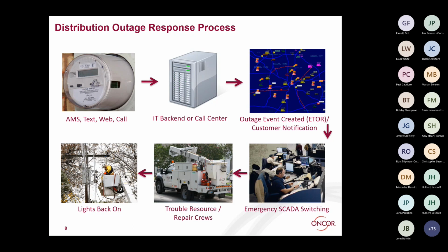Actually, what we do first, as the operations guy here, is we don't even patrol the line. We first try to isolate the exposure of that line. There's a protective device upstream that is opening up. Let's assume it's the breaker at the feeder in the substation, a hard fault, and the breaker opens up. The first thing the operator does is look at where the location could be. Did I get a 911 call? How can I dissect that feeder in half to see if the fault is downstream or upstream from the midpoint of the feeder? The first thing I do is try to isolate that fault. Where is it going on?